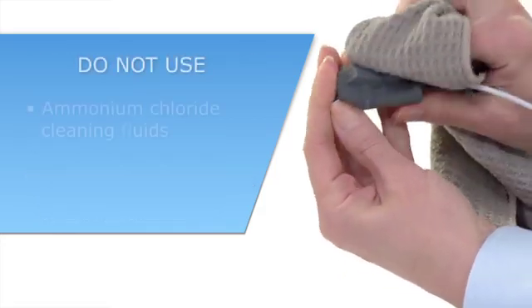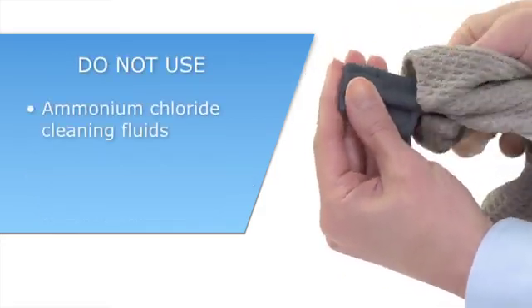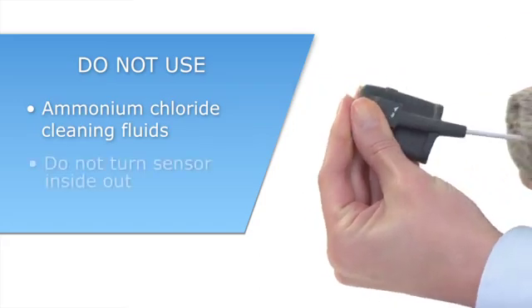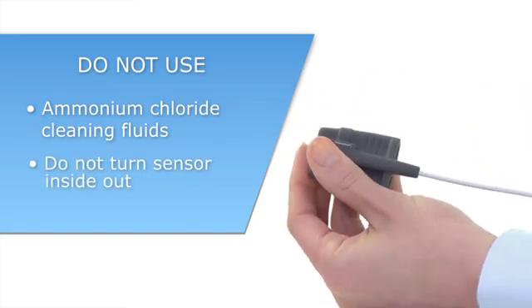Do not use caustic, abrasive, or ammonium chloride-based cleaners, which may shorten sensor life. Do not turn the sensor inside out, which may damage the silicone or sensor components.